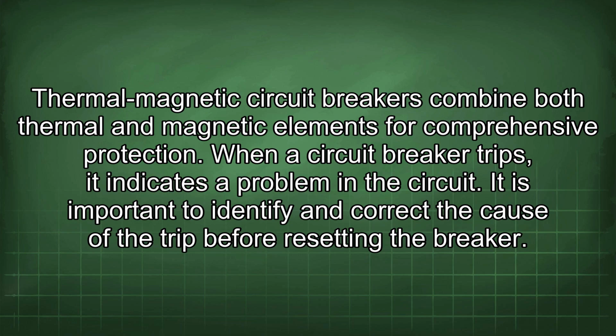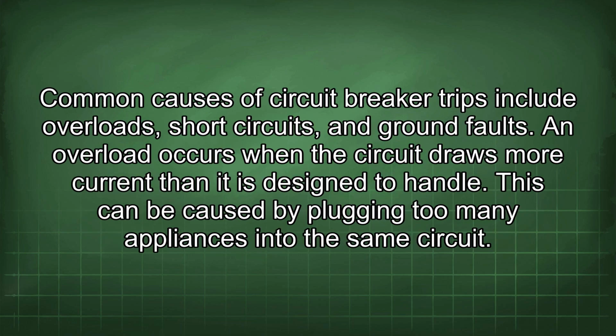When a circuit breaker trips, it indicates a problem in the circuit. It is important to identify and correct the cause of the trip before resetting the breaker. Common causes of circuit breaker trips include overloads, short circuits, and ground faults. An overload occurs when the circuit draws more current than it is designed to handle. This can be caused by plugging too many appliances into the same circuit.